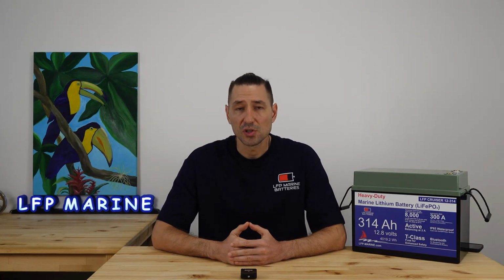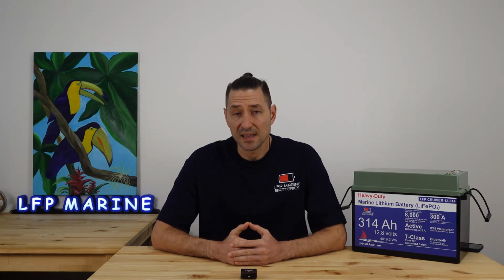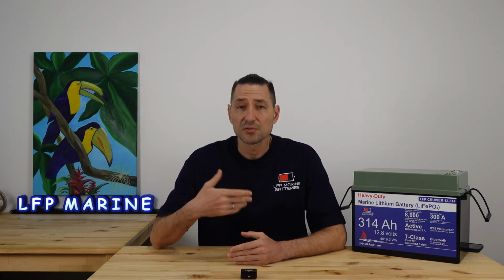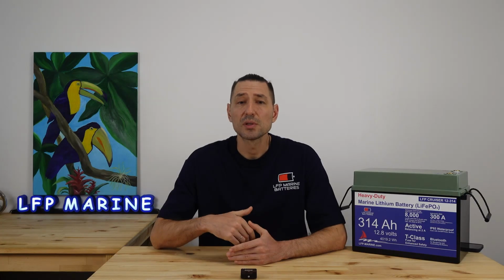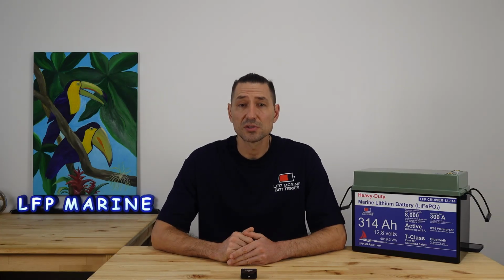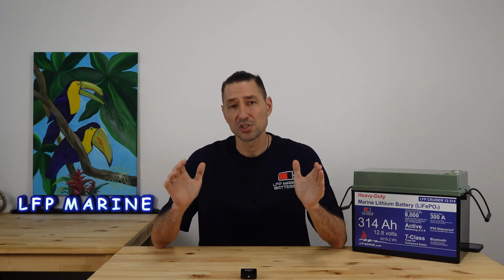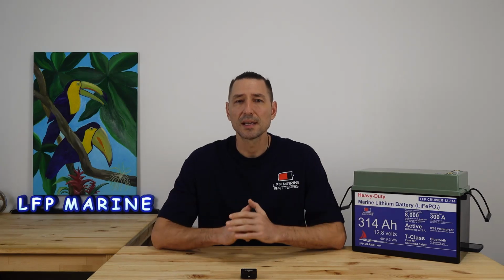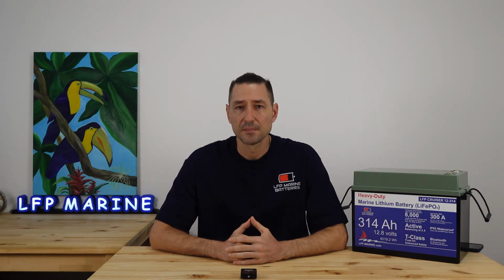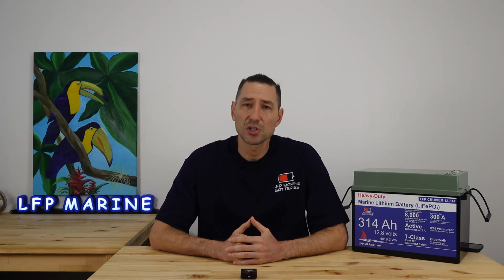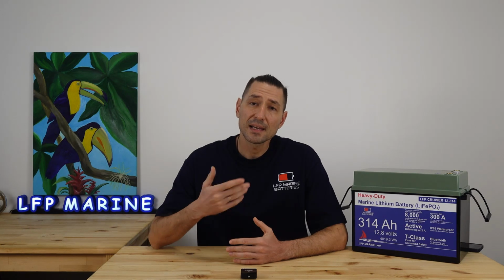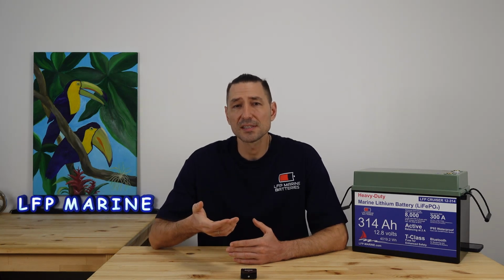A marine battery is typically a battery designed for heavy, long-term operation in harsh conditions. And these harsh conditions shorten its lifespan. To extend the service life, first, we use cells with the maximum number of cycles, 8,000. Second, when assembling cells into a module, according to the manufacturer's guidelines, we apply compression, thereby increasing the stability of the electrode's operation. In regular batteries, actual compression is generally not used, and in that case, the real number of battery cycles will be significantly lower.